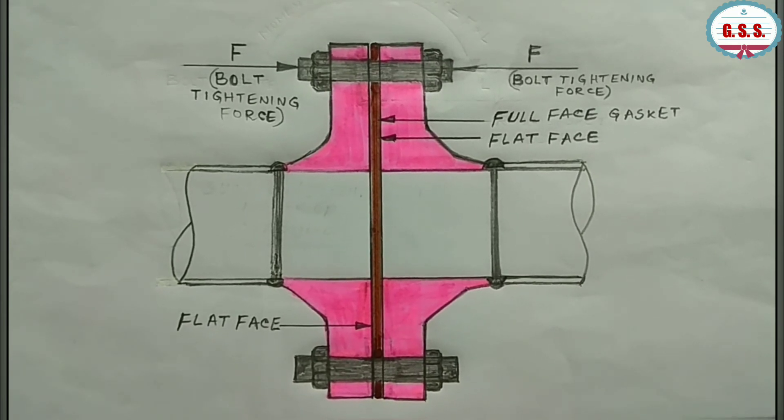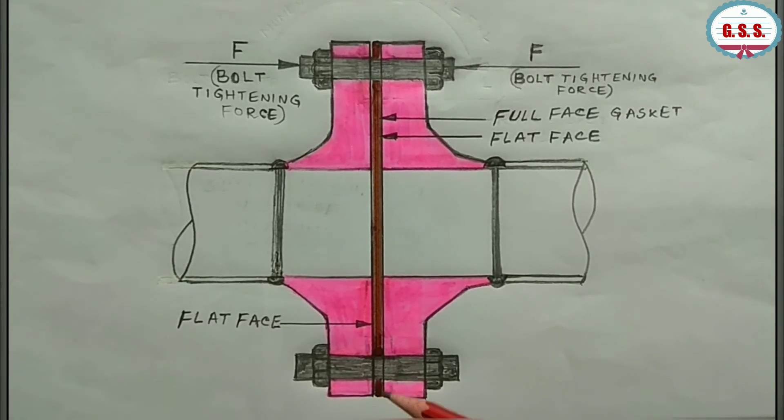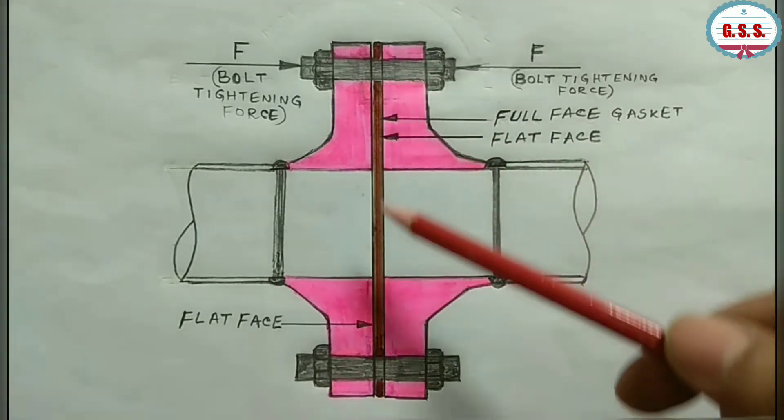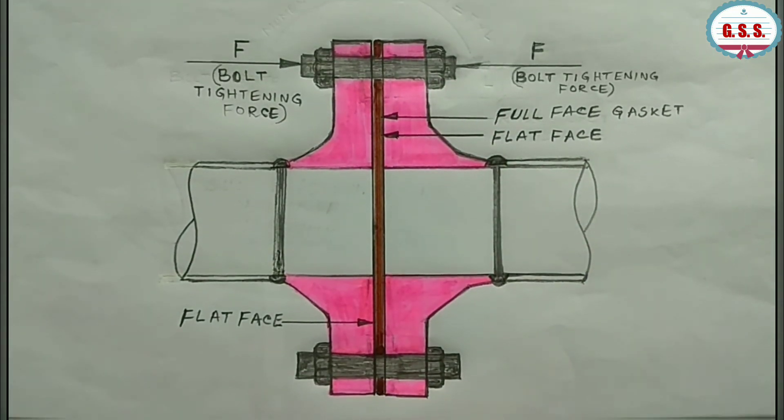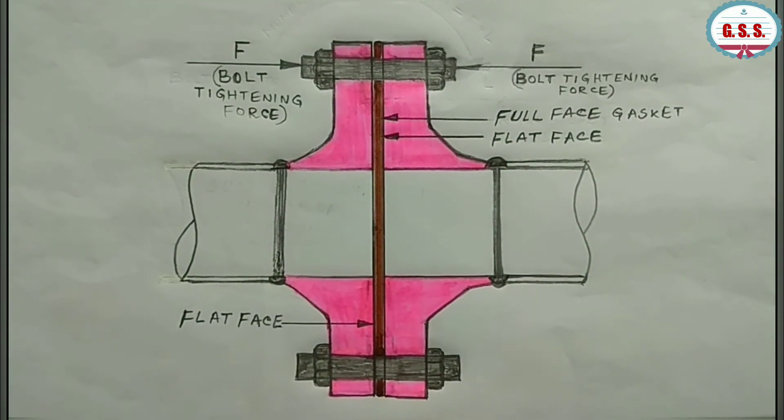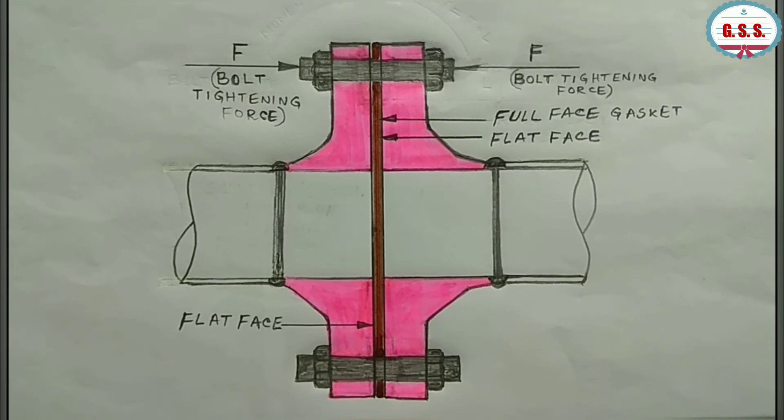In flat face flange, since the gasket seating surface is more, the gasket compressive load is less. Hence, the chance of leakage is more compared to raised face flange.